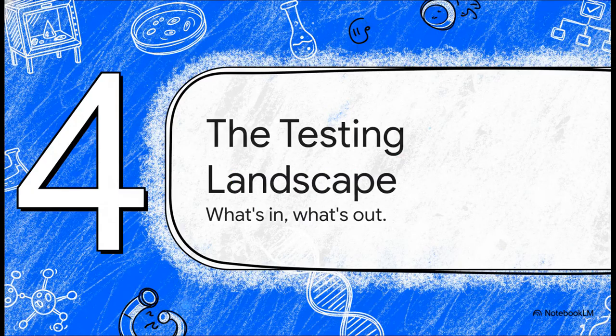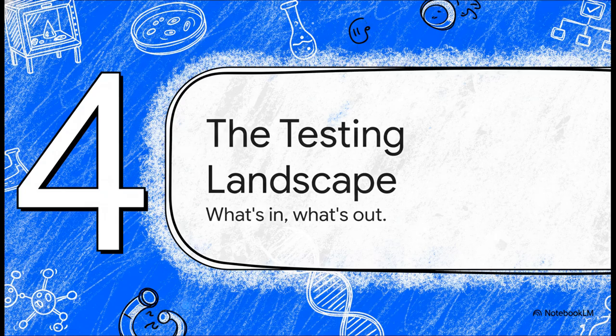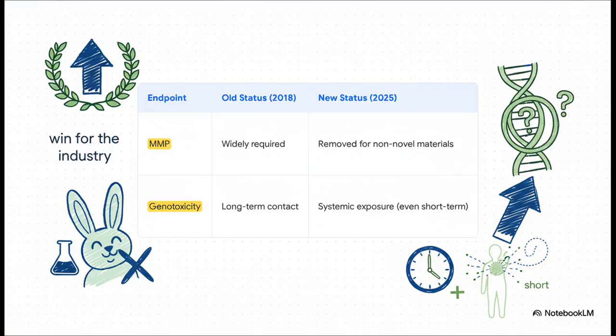All right. So with all these philosophical shifts and new rules, what does it actually mean for the tests we run day to day? Let's take a look at the new testing landscape for biological effect endpoints. Here are two of the absolute biggest shifts. First, and this is a real win for the industry, the material-mediated pyrogenicity test, you know, the rabbit pyrogen test, is pretty much being removed for devices made of common, well-understood materials. That's great news. On the other hand, the consideration for genotoxicity has really expanded. It's not just for long-term implants anymore. Now it has to be evaluated for basically any device that has potential systemic exposure, even if it's only short-term.